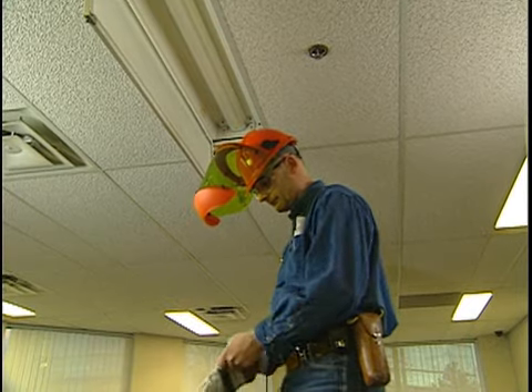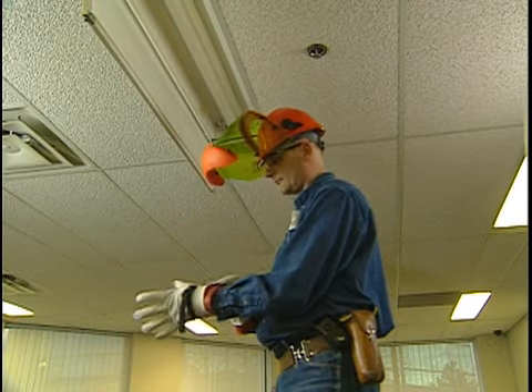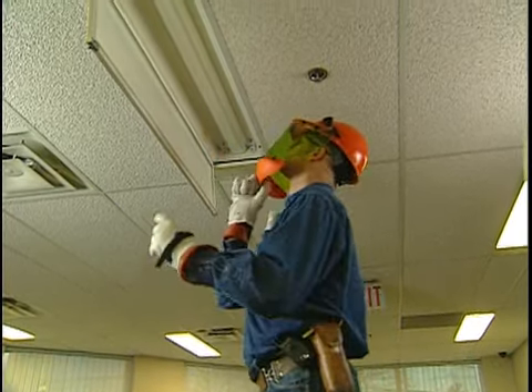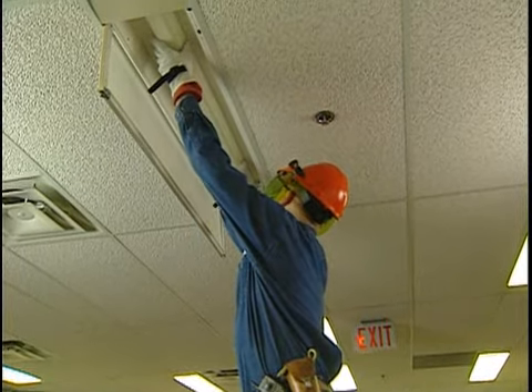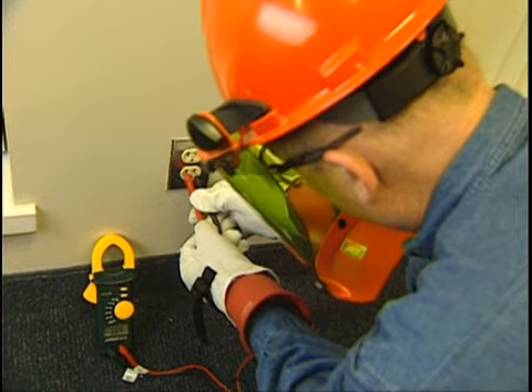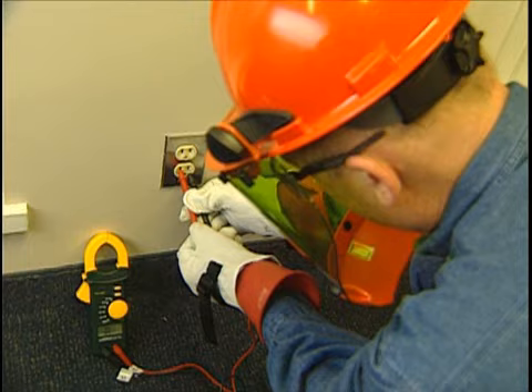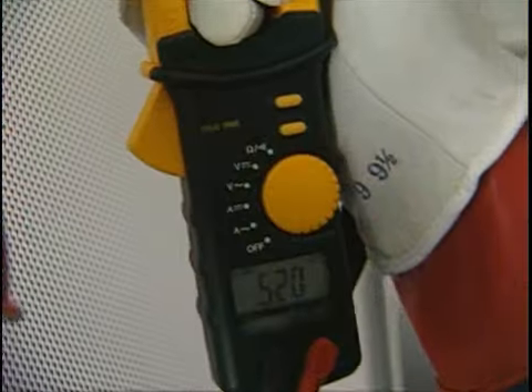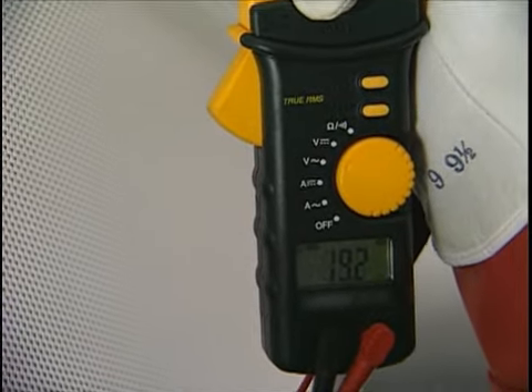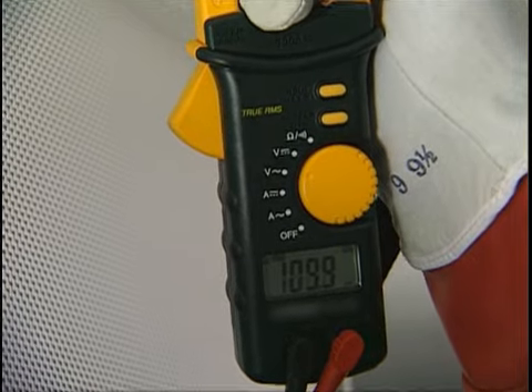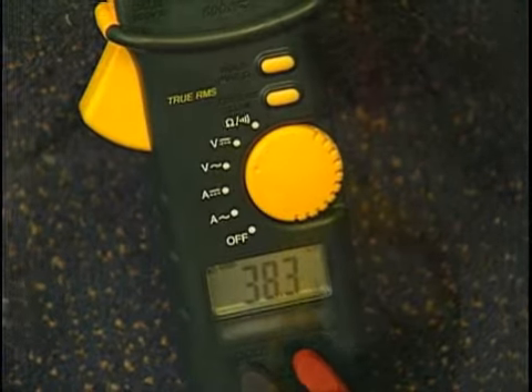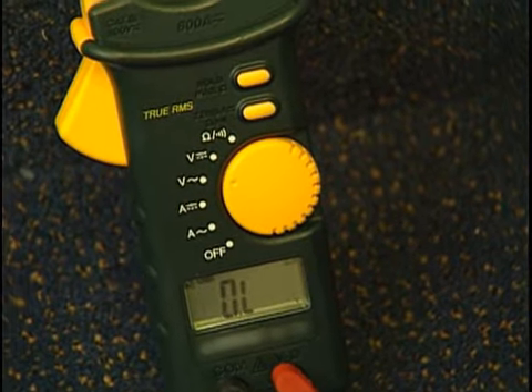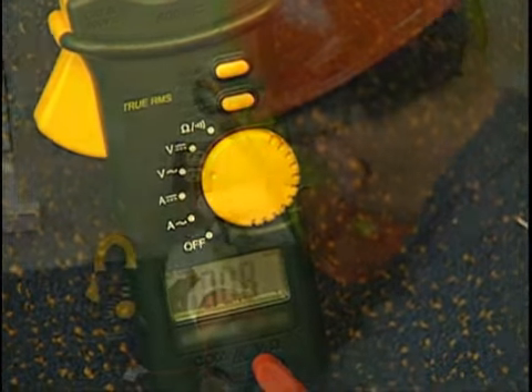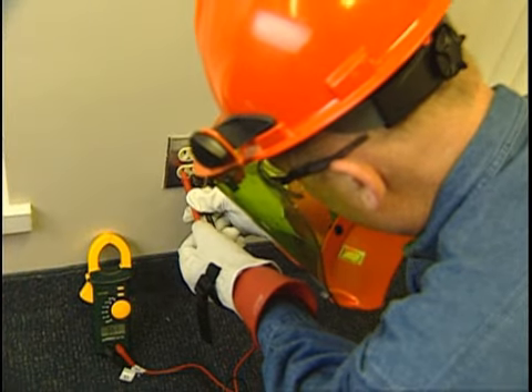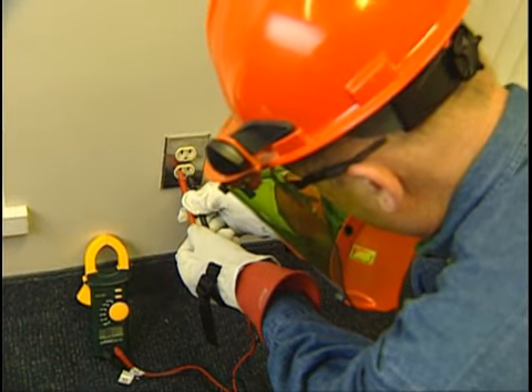Check for power at the device using a properly rated meter. The testing procedure that should be followed requires that you: 1. Test the tester on a known circuit. 2. Test live on the circuit you're working on. See if it's energized. 3. Go back and test the known circuit for verification. Proper testing is a key safety component.